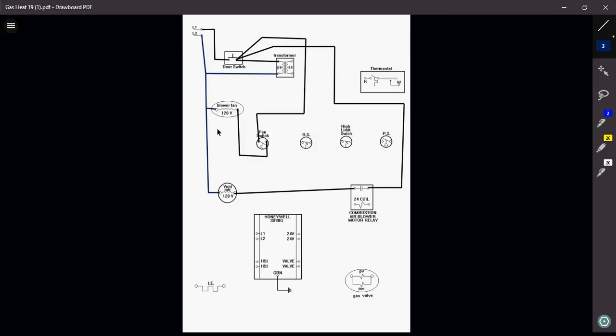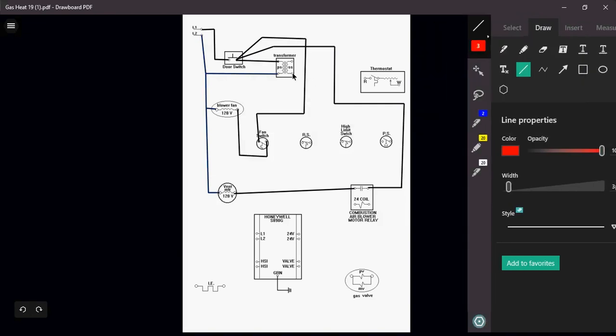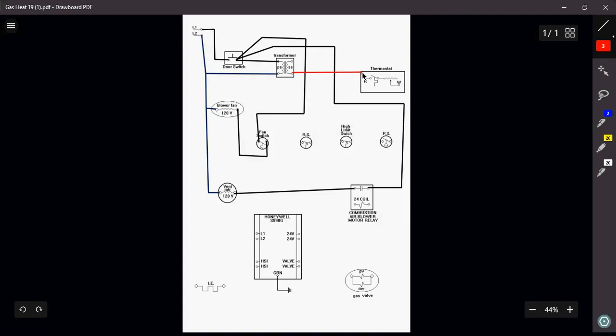Okay, well, I have my safeties, my rollout switch, my high limit switch, and my pressure switch. Okay, I have a 24-volt coil, and a majority, if not all, of your residential, light commercial heating units, all of your pressure switches, all of your safeties are going to be wired with 24 volts. 24 volts is our control circuit. Okay, so where am I going to be getting my 24 volts from? My 24 volts is going to be coming from the secondary side of my transformer.